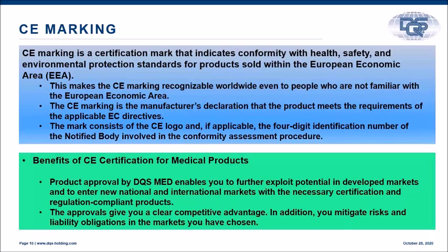If you see a CE mark with a 4-digit number, that means there is a notified body involved in assessing the product and the process compliance, and they grant the certificate to the manufacturer. Based on that, the manufacturer applies the CE mark on the product with the identification of the notified body who gave the approval.